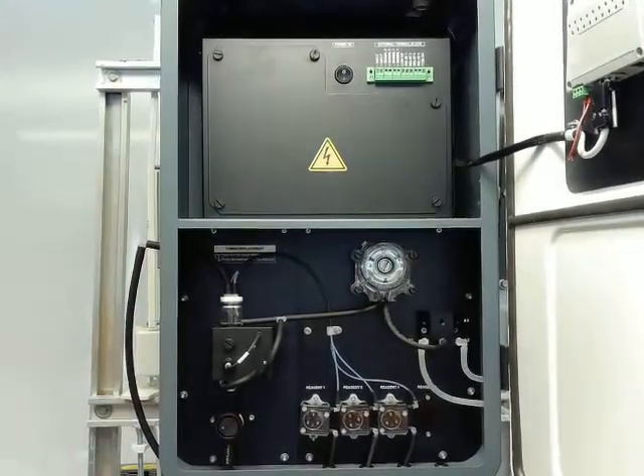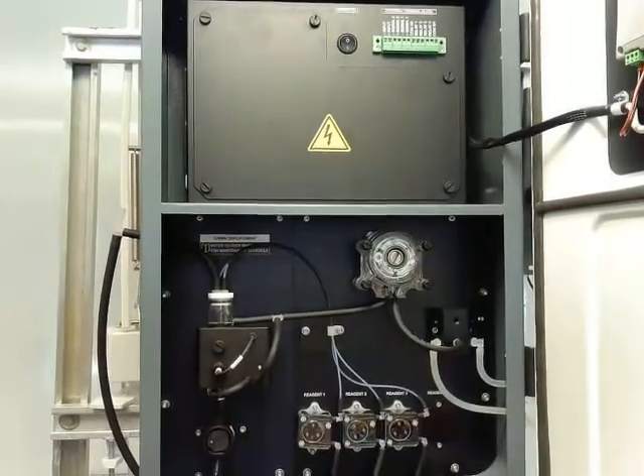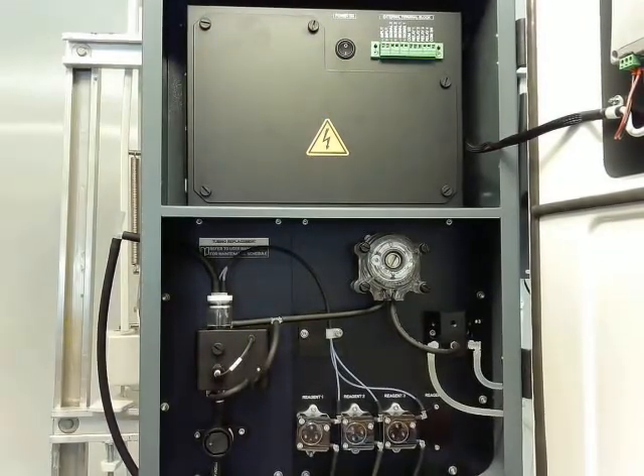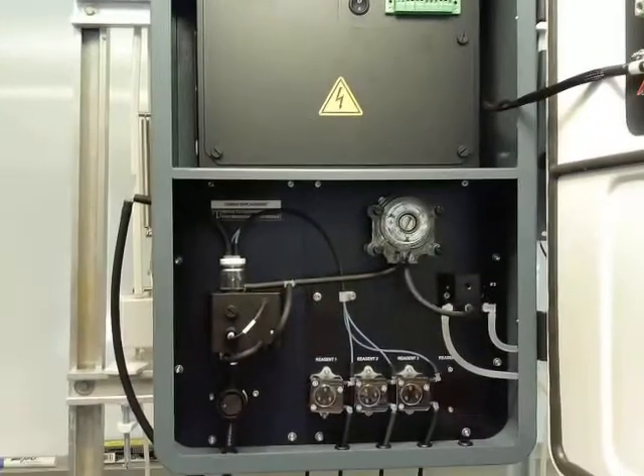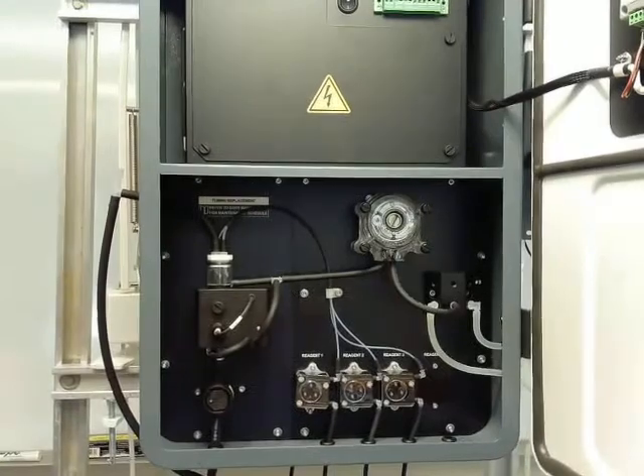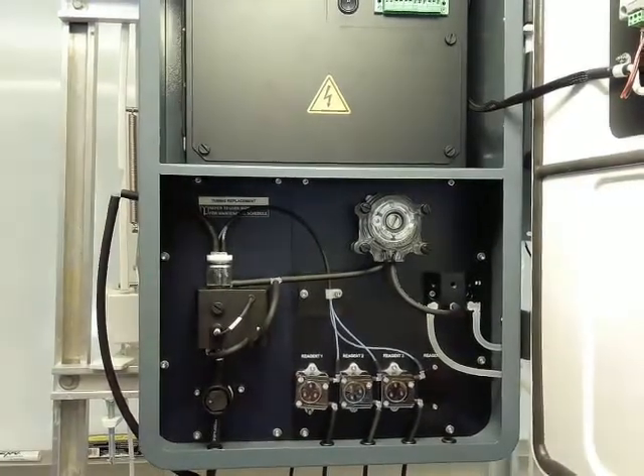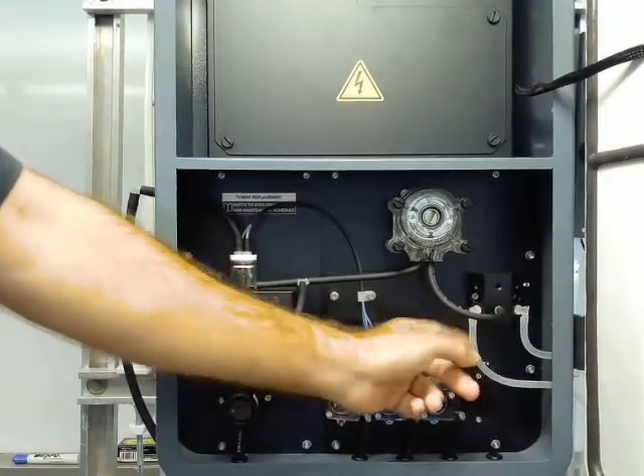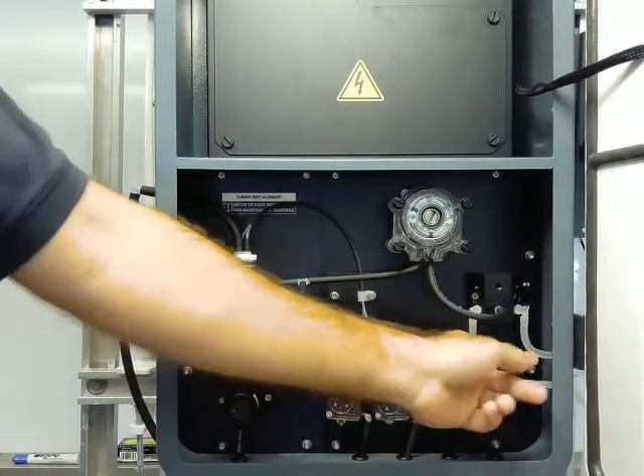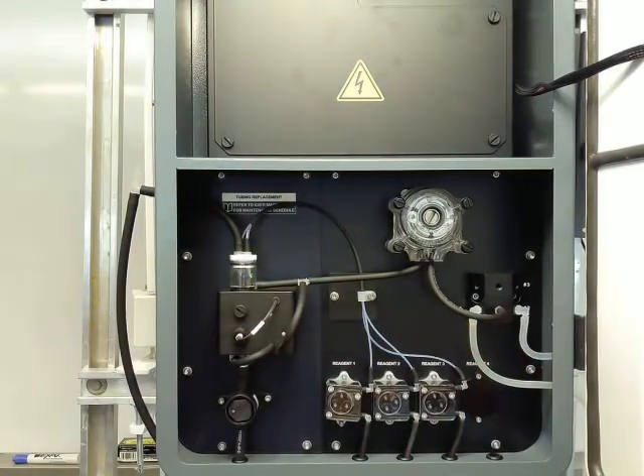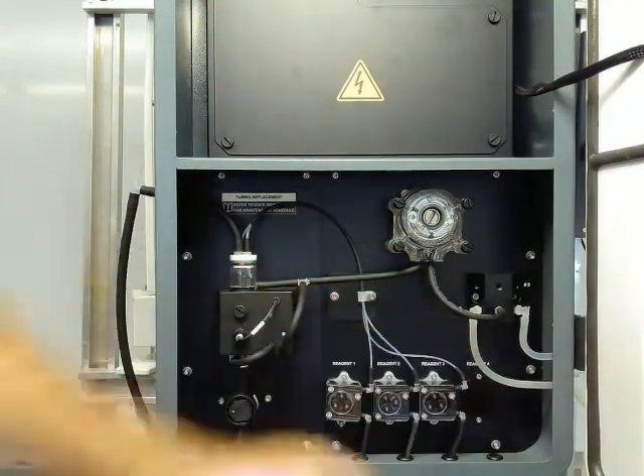So we open up our analyzer here. Again, we can see up top we have our electronics, power switch, and our terminal block for any 4-20s, alarms that we want to connect up. And at the bottom here, we have all of our pumps and other components. On the selection block, this tube on the number 1 port is for your sample line going to that fast loop reservoir. In the case of the copper analyzer, port number 2 would be going into our calibration standard below the analyzer. The monochloramine won't have that cal tubing. It'll really just have your tubing right to your sample pump for your inlet.